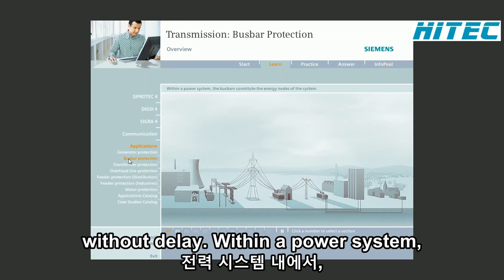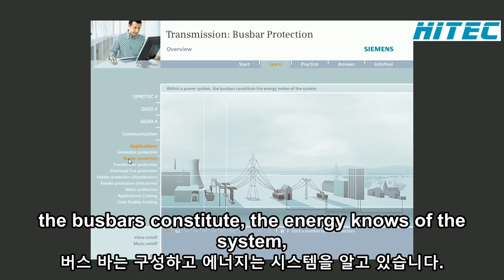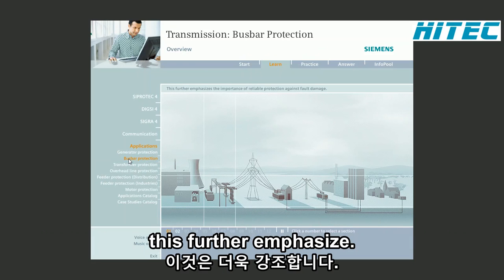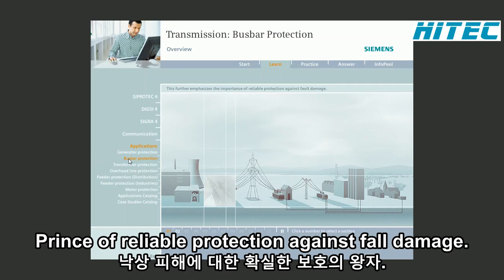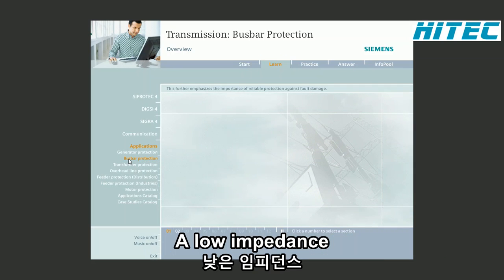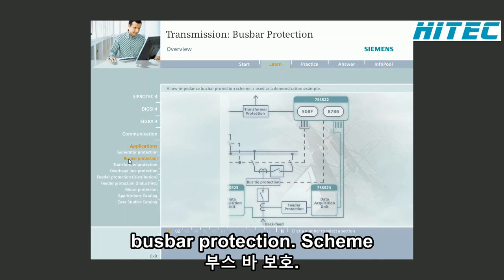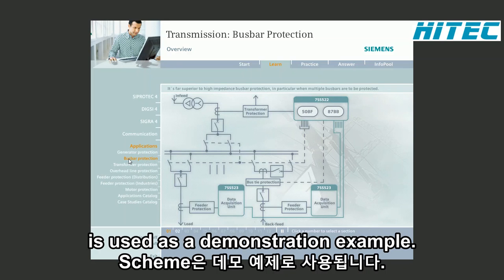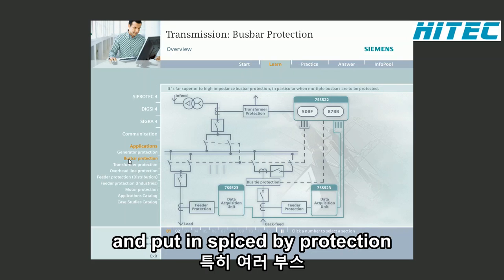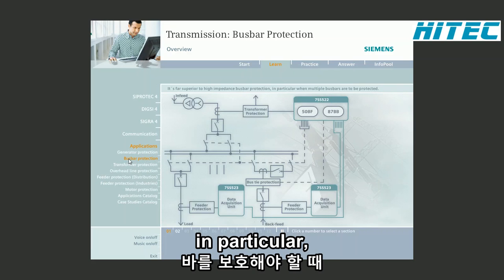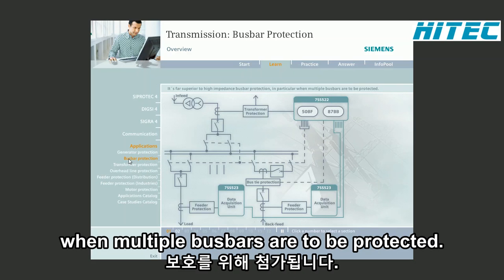Within a power system, the bus bars constitute the energy nodes of the system. This further emphasizes the importance of reliable protection against fault damage. A low-impedance busbar protection scheme is used as a demonstration example. It is far superior to high-impedance busbar protection, in particular when multiple bus bars are to be protected.